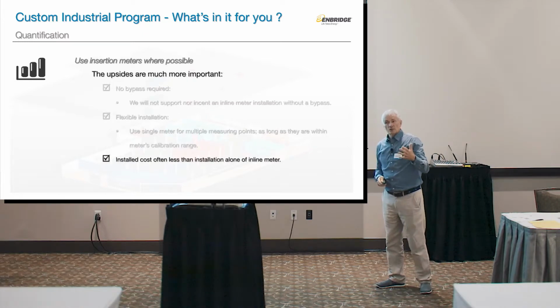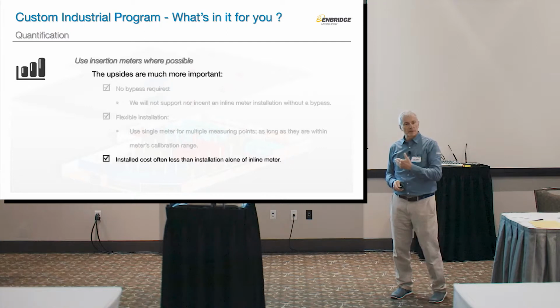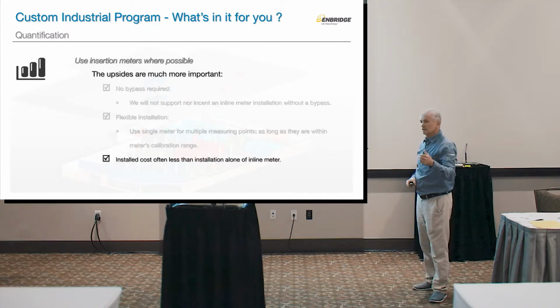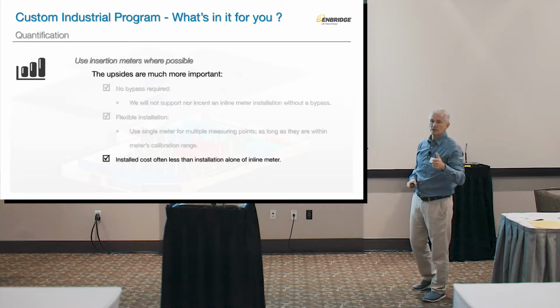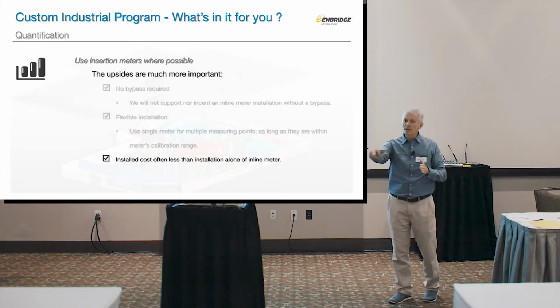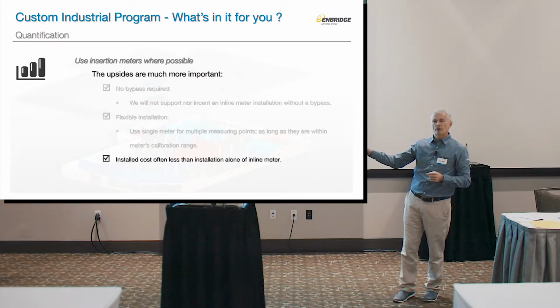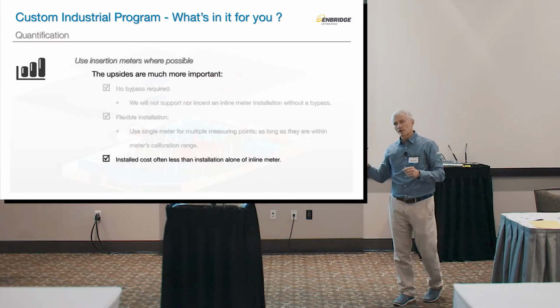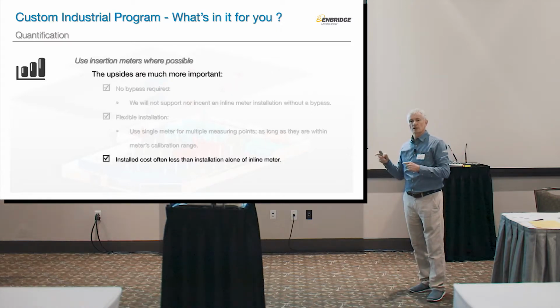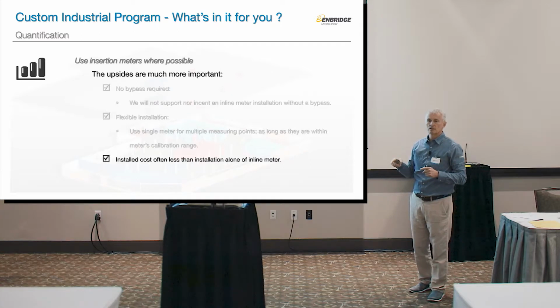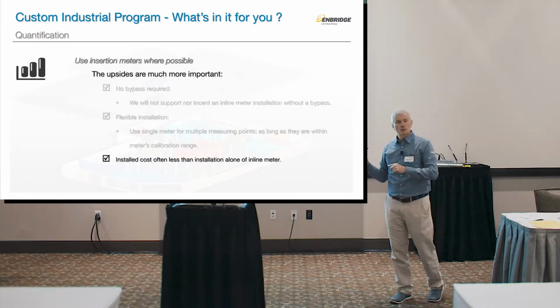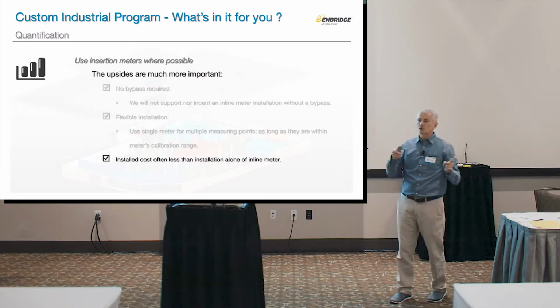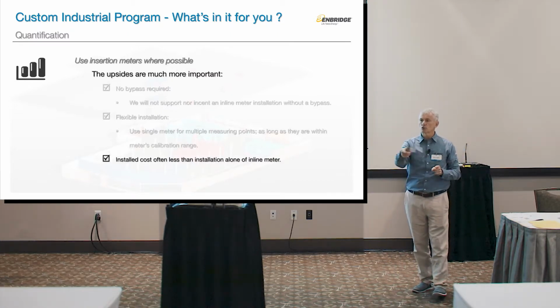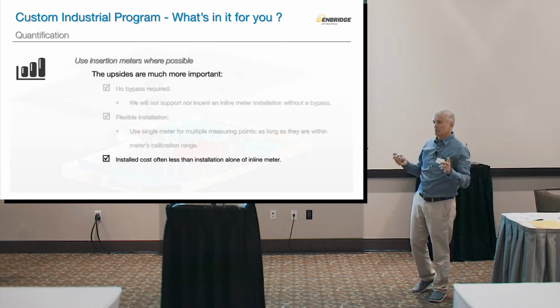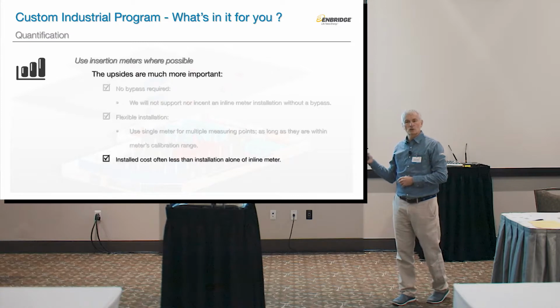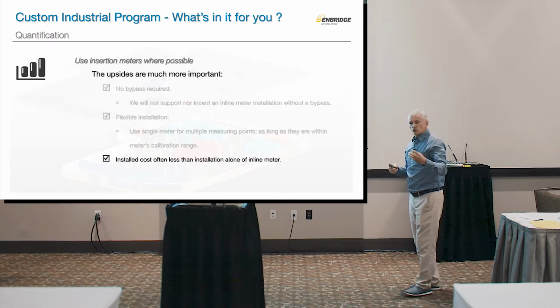What's important about this meter that an inline meter doesn't have? One is no bypass is required. With an inline meter, you have to cut your pipe, and if you don't put in a bypass in case the meter fails, your equipment will fail and you won't be able to run it. So as a rule, we won't give incentive for an inline meter unless you're putting in a bypass. We learned that the hard way, we were sued once because a customer's equipment was down when the meter malfunctioned. Even though we told them to use the bypass, they didn't want to. Remember, putting in a bypass adds another $3,000 or $4,000 to the cost, so in the end it costs more.